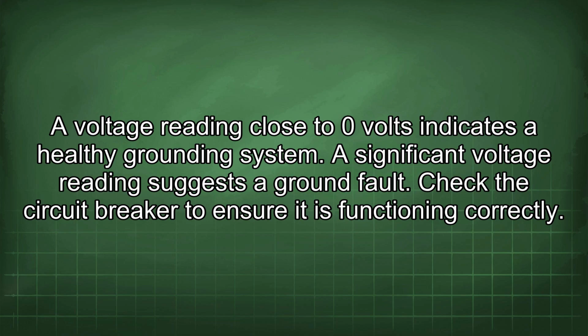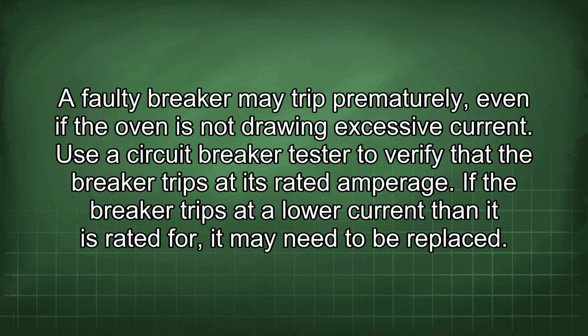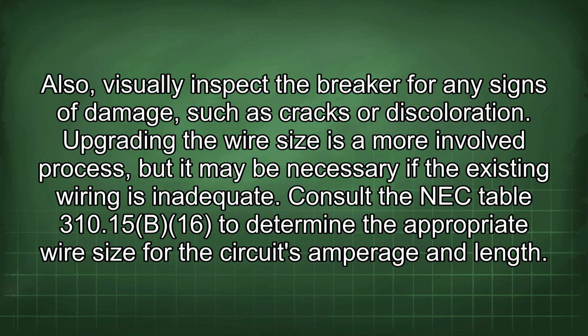Check the circuit breaker to ensure it is functioning correctly. A faulty breaker may trip prematurely, even if the oven is not drawing excessive current. Use a circuit breaker tester to verify that the breaker trips at its rated amperage. If the breaker trips at a lower current than it is rated for, it may need to be replaced. Also, visually inspect the breaker for any signs of damage such as cracks or discoloration.